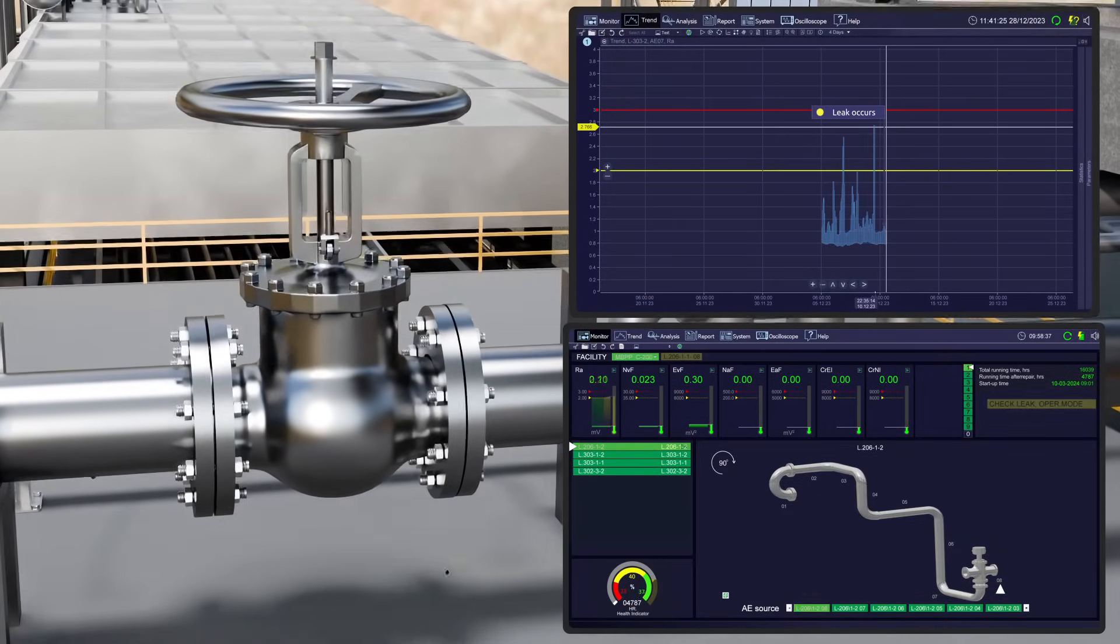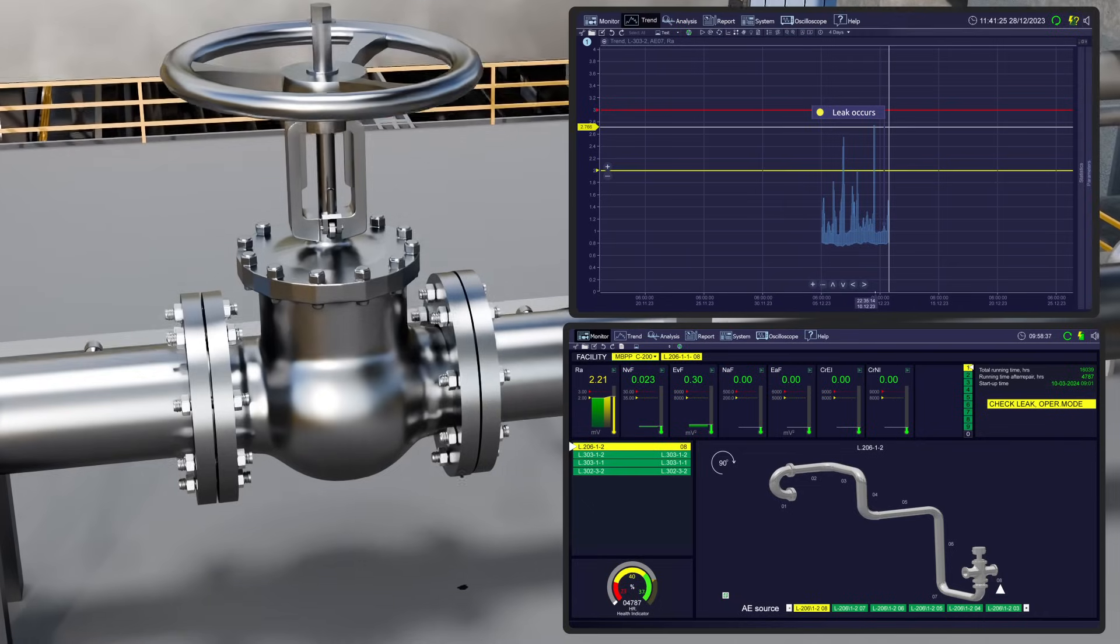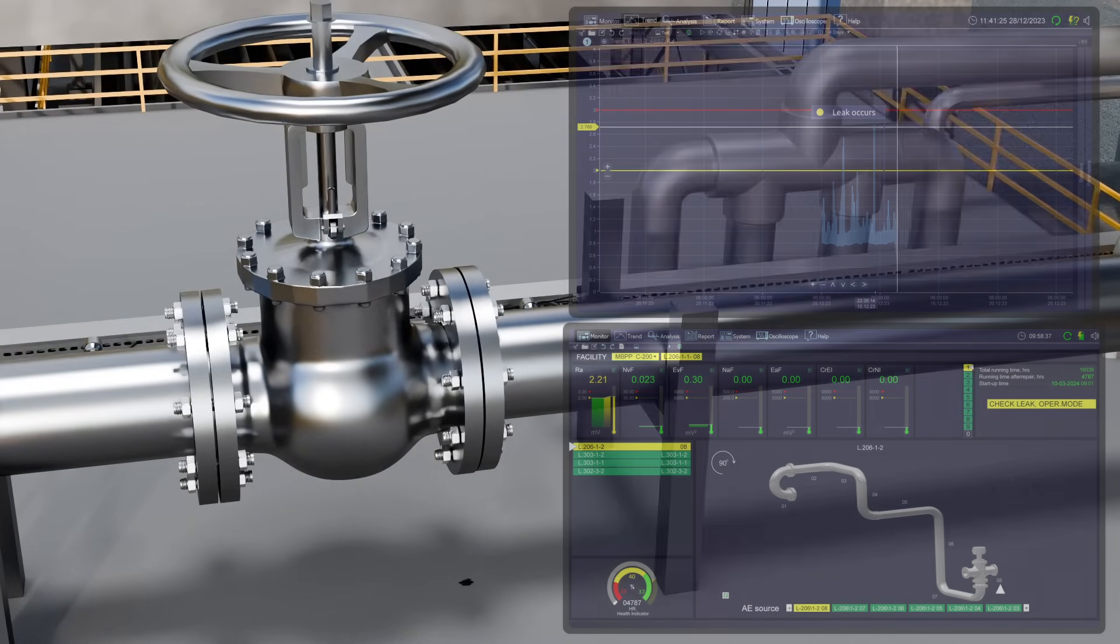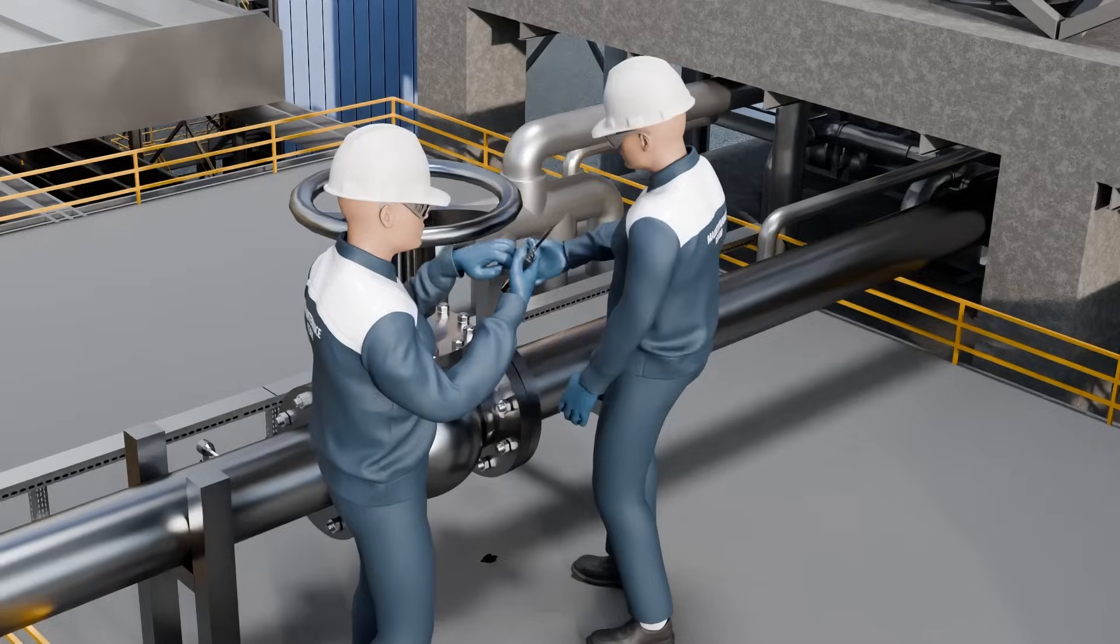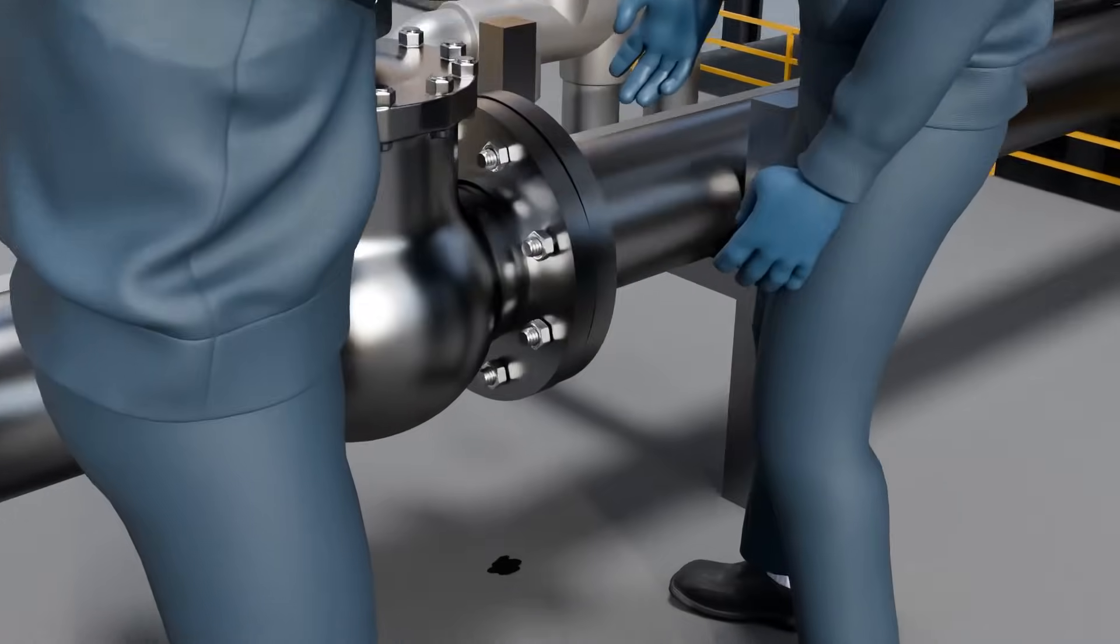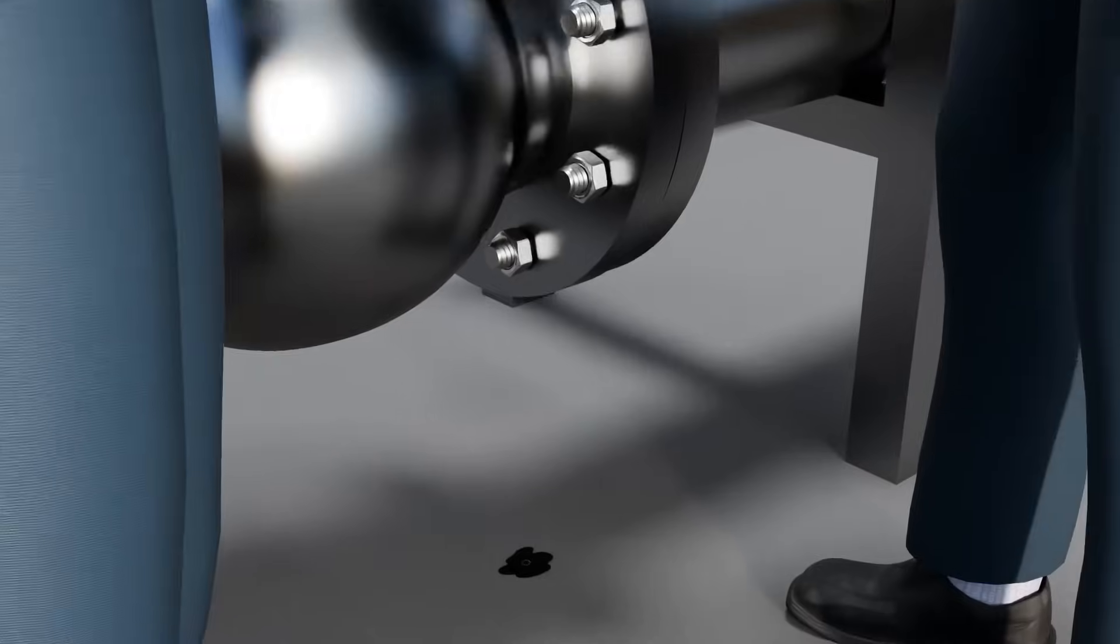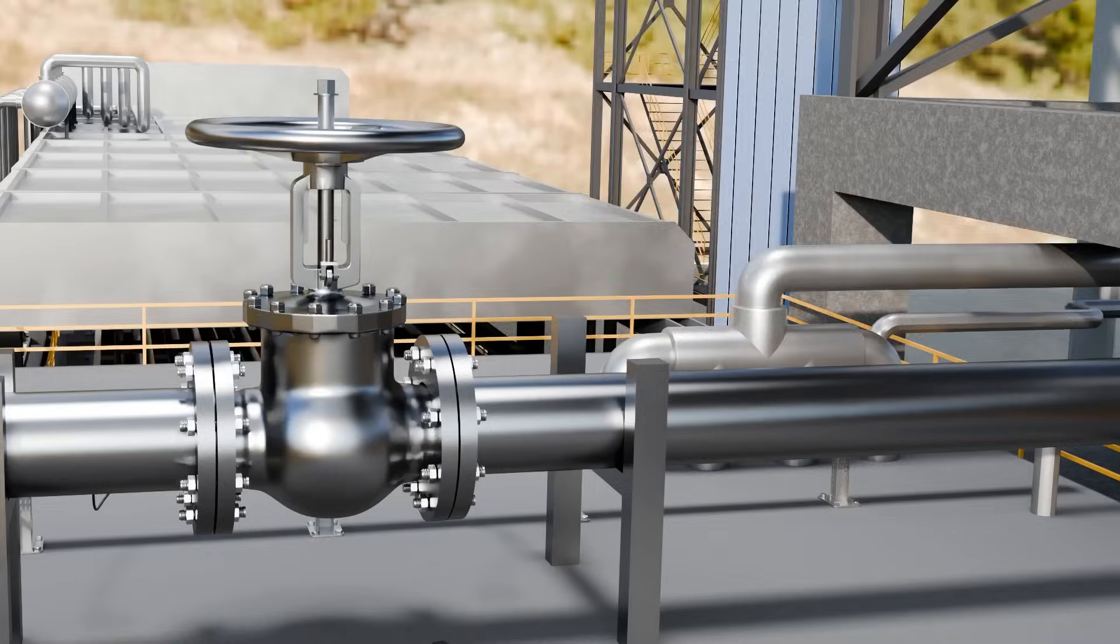On December 5th, the compact system detected and tracked an abnormal spike in the acoustic emission parameter, indicating the beginning of a leak. After inspecting the pipeline section near the corresponding sensor, the maintenance personnel found a minor leak in the process valve installation area.